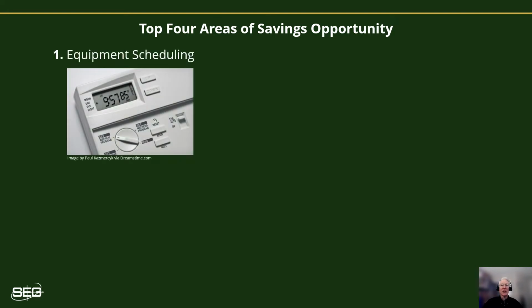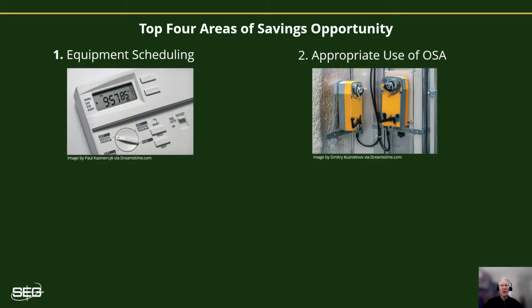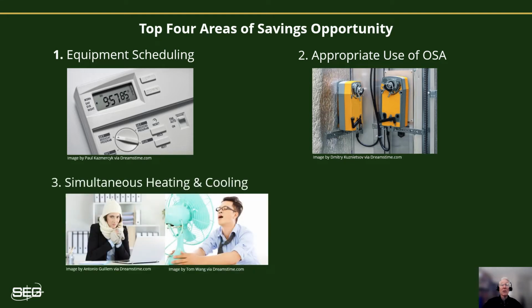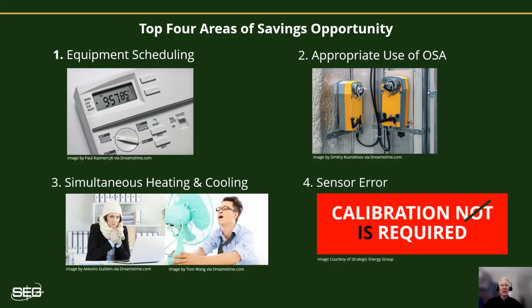These 4 items are widely recognized as top areas of savings opportunities in existing buildings: equipment scheduling, appropriate use of outside air, simultaneous heating and cooling, and sensor calibration. You may have noticed that all 4 of these involve only the HVAC systems.